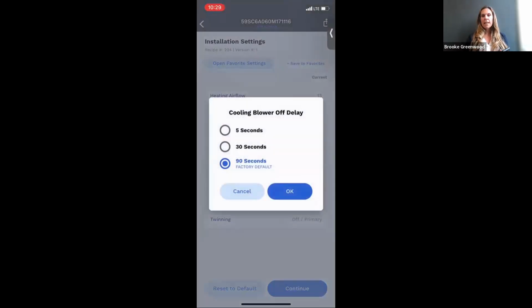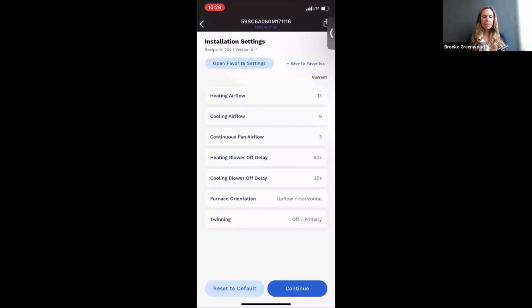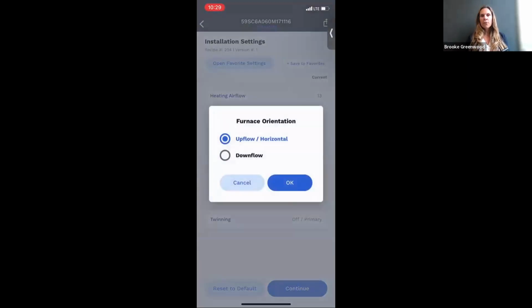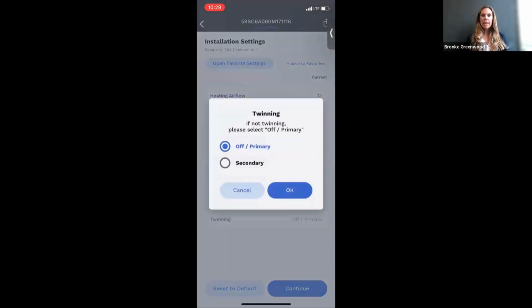Cooling blower off delay, very similar type settings. I'll make an adjustment there just for the fun of it. Again, your orientation, upflow or horizontal, doesn't do anything to the screen - it stays the way it is. But if you go to downflow, it flips it for you for when it's installed. And then again, we talked a little about twinning, still needing your kit, but here's where those selections look like to set your primary or off if you're not twinning, and then secondary.